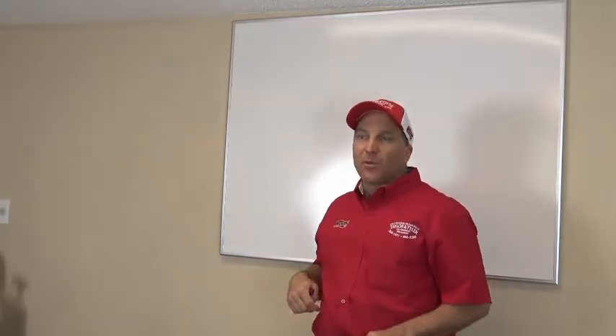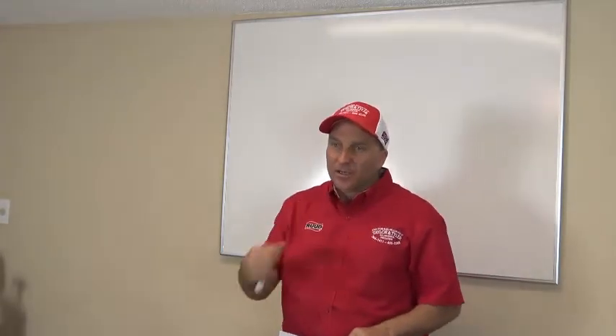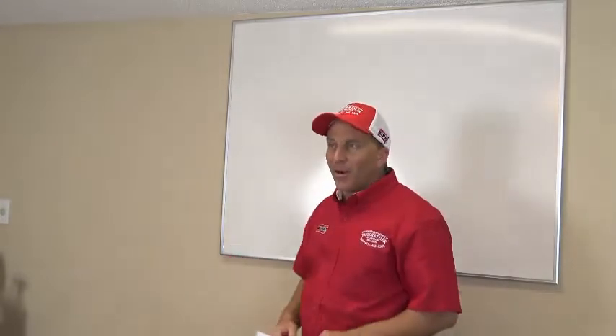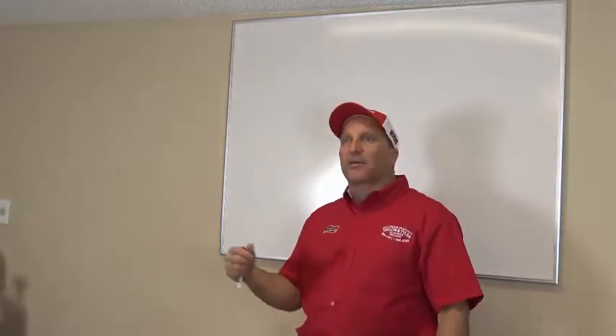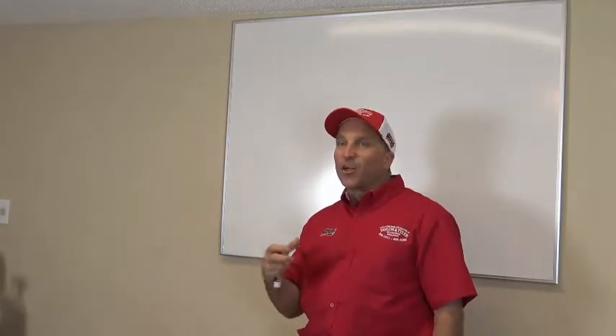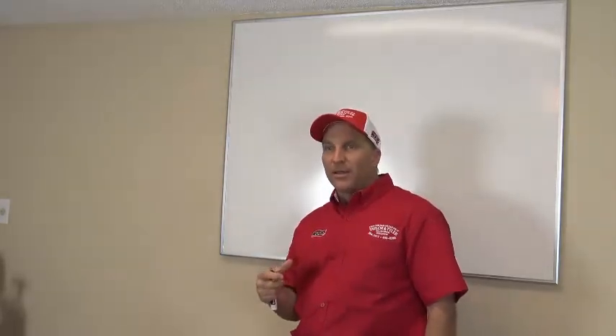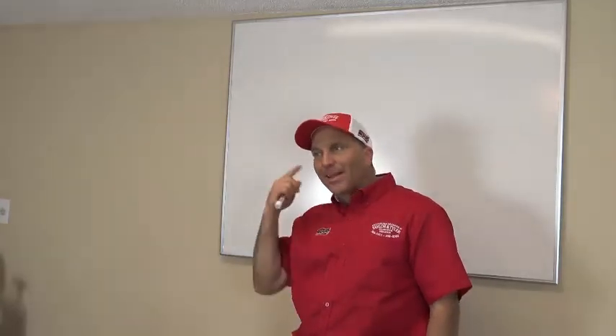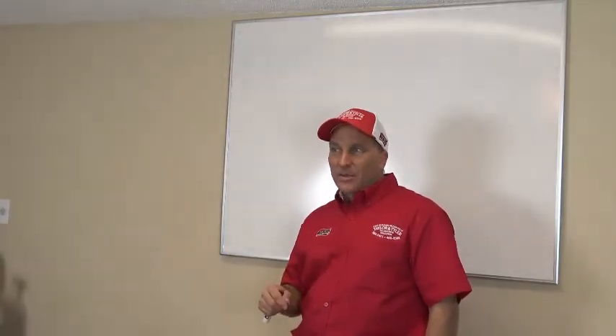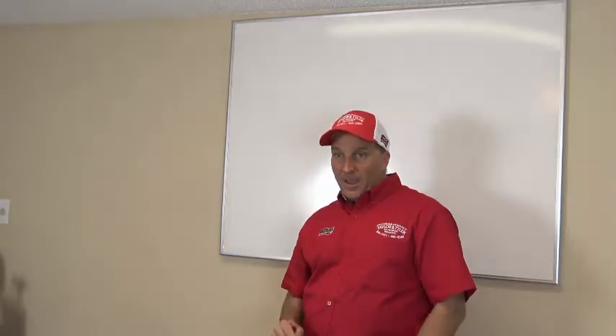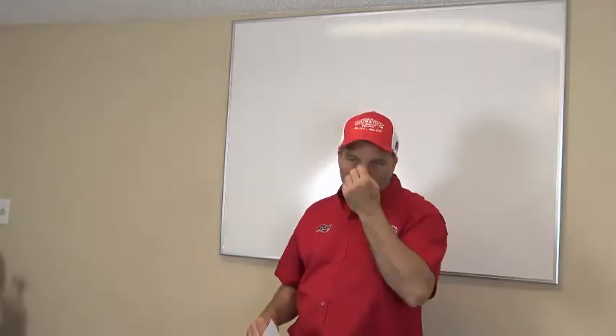Now, here's what can happen with a scroll compressor. You turn the system off real quick and turn it right back on, and you hear that compressor go, and it's running and makes a lot of noise when it's running. Okay? It's running backwards. And if you've got gauges on the system, I know what that sound is. And I'll tell you, there was a job right over here in Harvey. I went over to it, and I had to kill the power for just a second to do something. I forgot what I was doing.